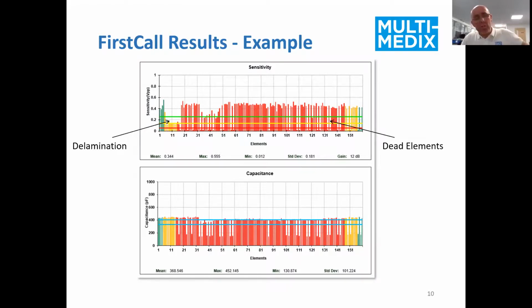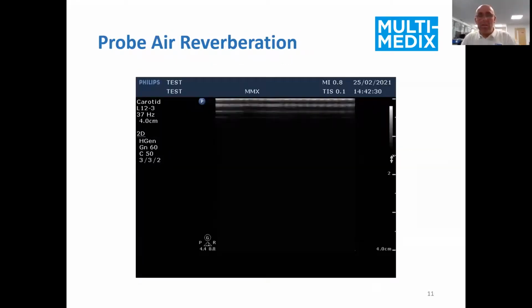But what does this probe look like in real use? Well, one of the strangest things is, whilst we can see this is very defective and we've got lots of dead elements, this is what the initial image looks like in the air reverberation, ready to do a standard carotid exam. And whilst I, as a very experienced person looking at probe performance, can start to see degradation in that reverb pattern, a lot of people might just get gel on that and put it on the patient, and that may mean that they miss clinical information. However, with careful optimization of the ultrasound scanner settings, we can actually really see the impact of what our FirstCall report showed. So I'm going to show that on the next slide.